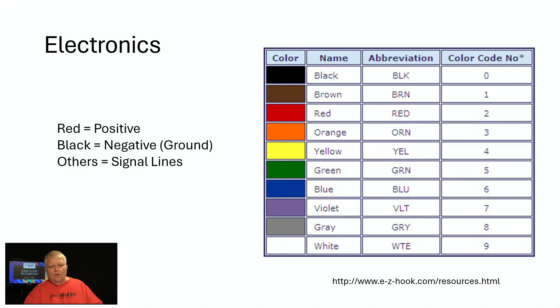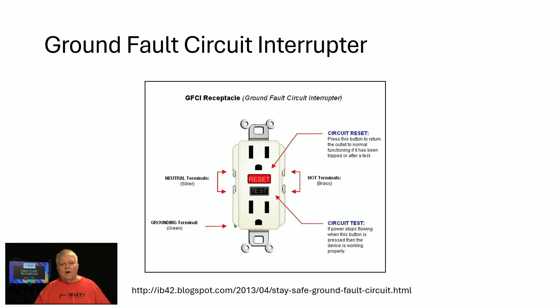With electrical circuits, especially in damp areas or near plumbing fixtures, something called a GFCI, a ground fault circuit interrupter, is very popular now. The whole point of the GFCI is that the current flowing out of the black wire, through whatever device you're powering, and back through the neutral should be exactly the same. If it's not exactly the same, that suggests to the GFCI that there's a stray current going somewhere else, maybe through your body.